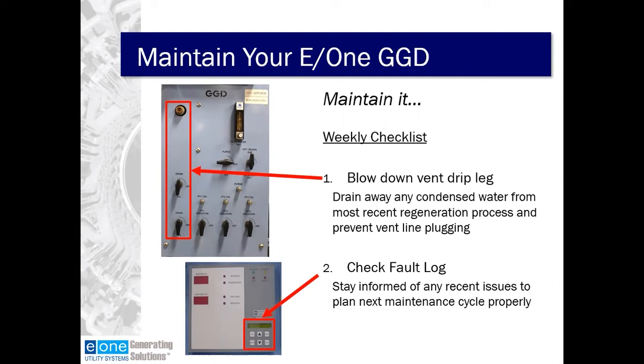Depending on your location in the world and what the ambient conditions are, that water vapor in the vent line will condense to some degree and flow back down the vent line. If you do not have a low point drain on that vent line, all of that condensation will form in a water collection area we have inside the dryer. Otherwise, we will only collect some or a portion of that water vapor that condensed in this catch pot. So we have a level indicator, a sight glass that you can look at to see if there's water in the containment vessel. And then we have two valves on the front of the panel as indicated in the upper picture there. You would open those valves to drain the water out of the vent line.